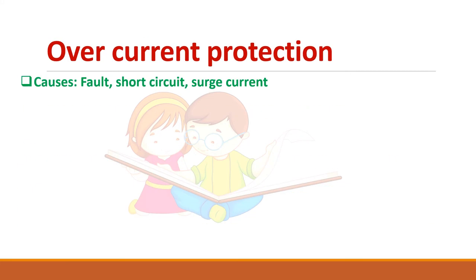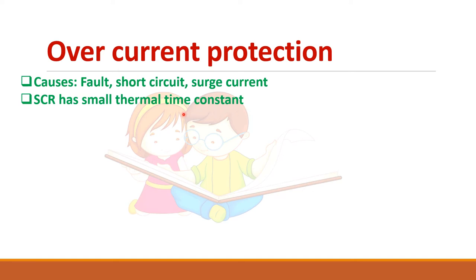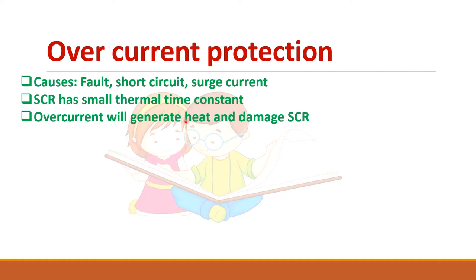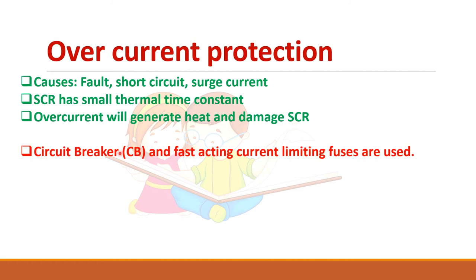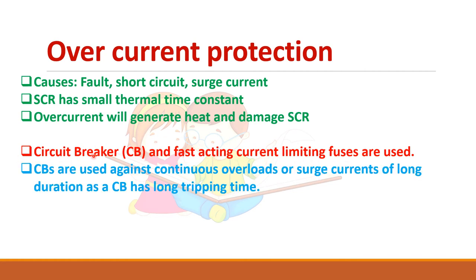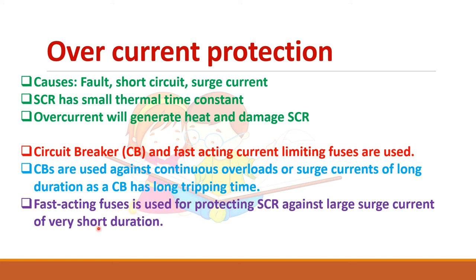The major causes for overcurrent are faults, short circuits, and surge currents. Since SCR has a small thermal time constant, it cannot carry more than the rated current for a long time. Overcurrent generates heat and damages the SCR. Normally circuit breakers and fast acting current limiting fuses are used. Circuit breakers protect against continuous overload or surge currents of longer duration, whereas fast acting limiting fuses protect against large surge currents of very short duration.